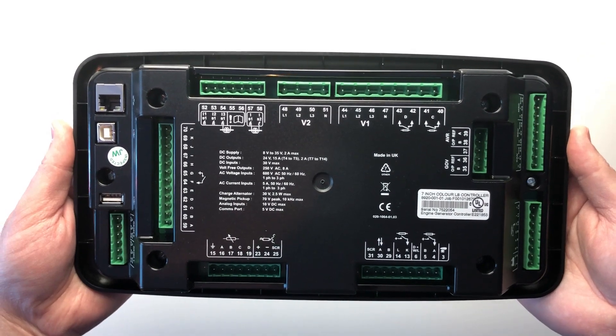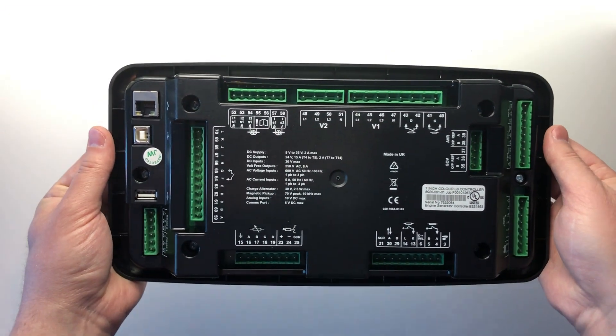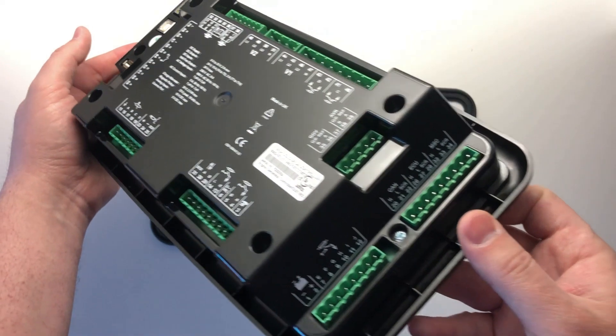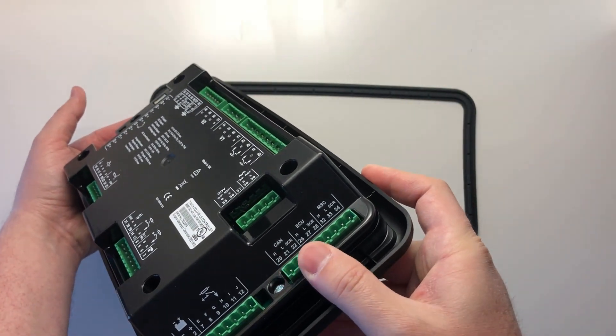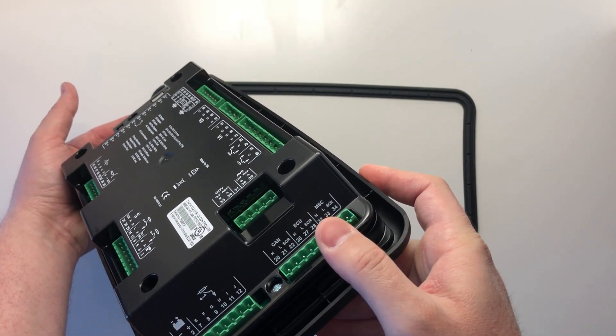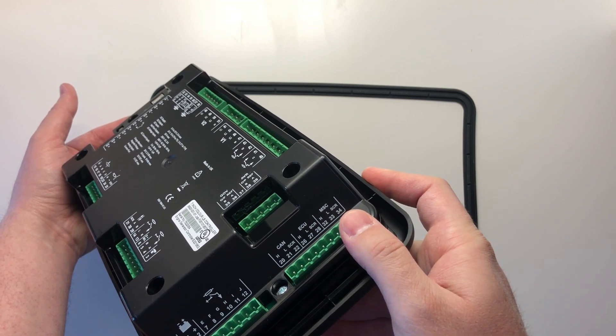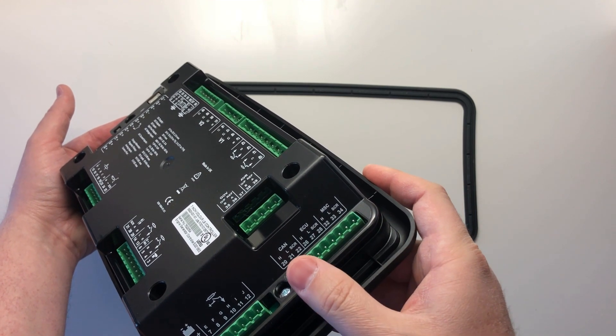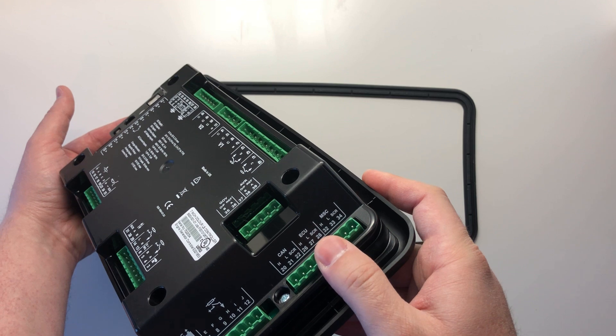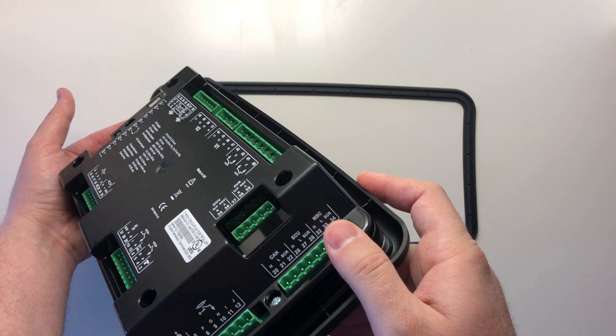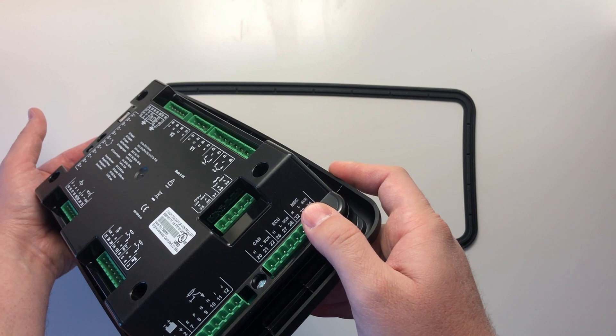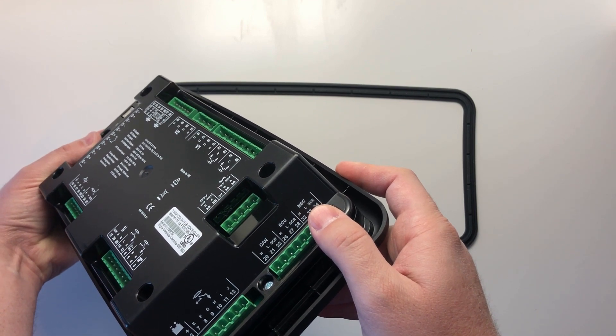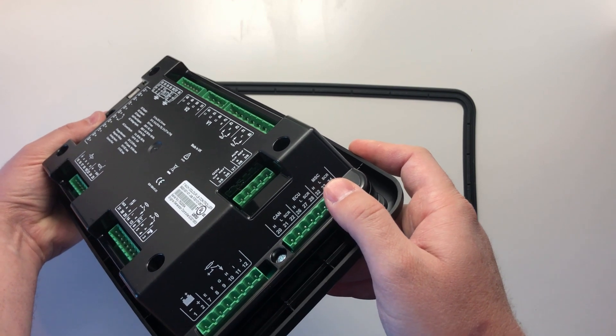We will now take a look at the communication ports on the module. Here we have the CAN bus port for connecting to other CAN devices or HMIs, the ECU port for communication with the engine control unit or ECM, which also supports Tier 4 Stage 5 engines, and the multi-set communication port or MSC for connecting multiple DSE load share controllers together for synchronizing and load sharing.